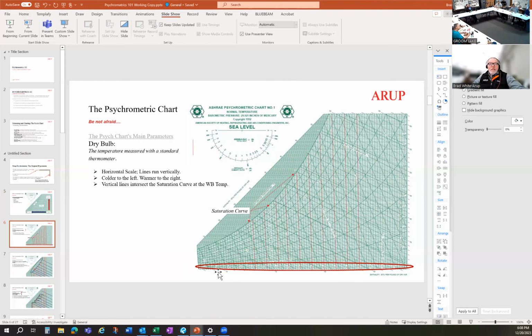Dry bulb, as the name implies, is strictly the reading of the dry bulb of a thermometer. The scale of this is along the bottom. The temperature goes colder to the left, warmer as you go towards the right. And the lines that index to this scale are vertical lines. So it's a horizontal scale, vertical lines. And they all end at the top at what's called the saturation curve. This is the point where no more moisture can be suspended in the air and it will condense. There's no air outside of this line with moisture in it.